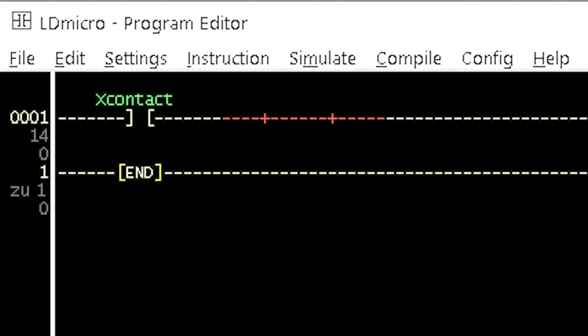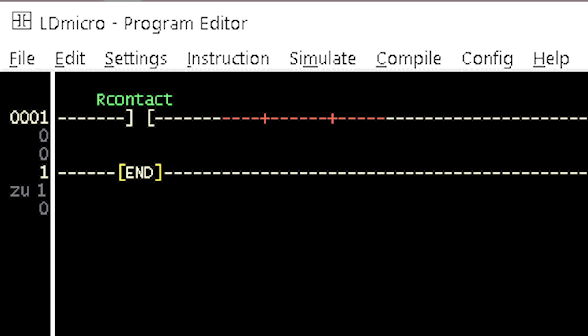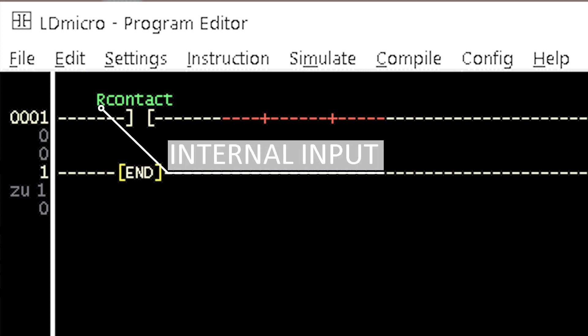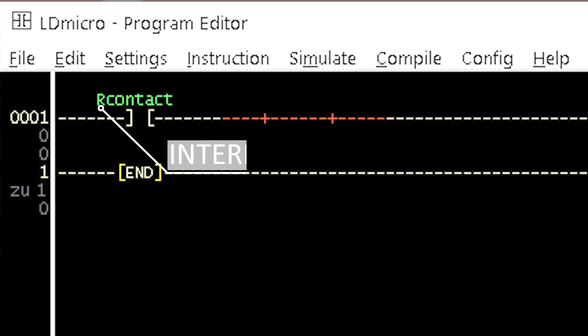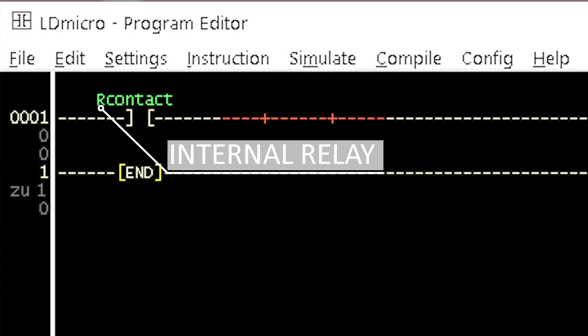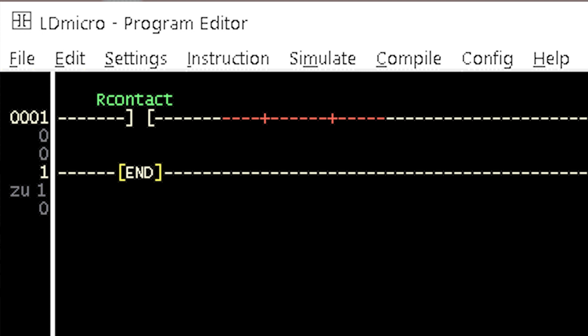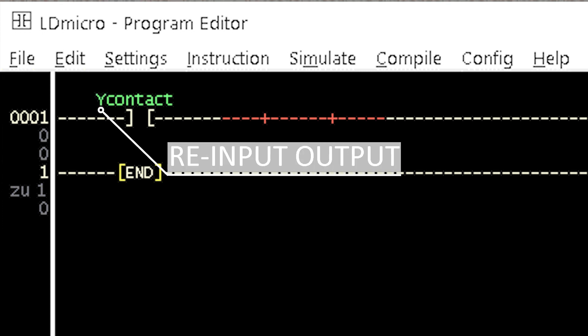First, contact. Contacts receive input signals from both internal and external sources. When the input is from an external source, the contact label or variable name starts with X. When the input is from an internal source, the variable name starts with R. A contact with an internal input source is called an internal relay. In some cases, the output of a ladder logic might be used as an input to another logic. In such cases, the variable name of the contact will begin with Y, which is also the beginning alphabet for coil variables.